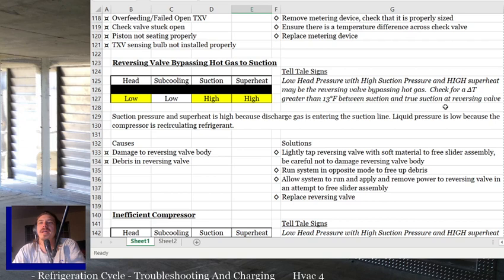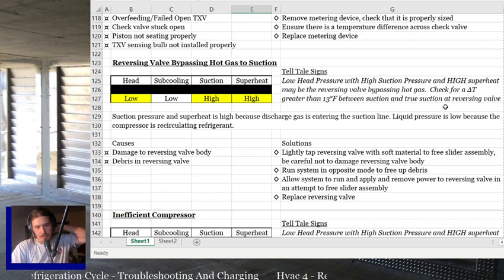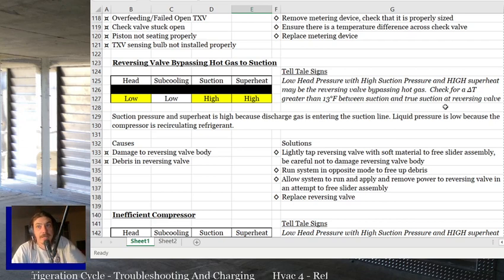Reversing valve, bypassing hot gas to suction. So these next two are the other things that will give you a low head pressure and a high suction pressure, but they have high superheat. Okay, so if you got low head pressure and a high suction pressure and low superheat, you're feeding too much refrigerant. But if you've got high superheat, then you've got a reversing valve issue or an inefficient compressor issue. If you're not working on a heat pump, then it's probably the compressor.